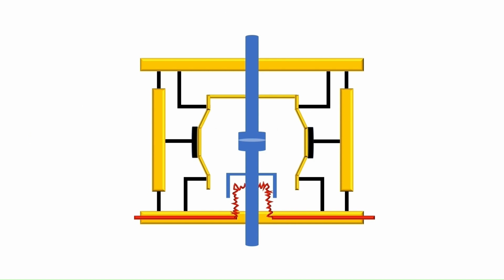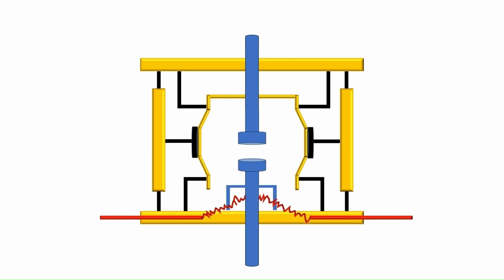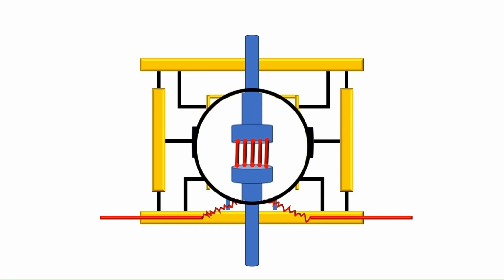When the fault occurs in the system, the contacts of the breaker are moved apart. When the moving and fixed contact detach, their entire surface does not separate simultaneously. During separation, the contact surface area gradually reduces before the contacts fully separate. As the contact area decreases, the current density increases at that point, creating a hot spot. At this hot spot, the contact metal vaporizes. So when the breaker contacts separate, an arc forms due to the ionization of the metal vapor released from the hot spot on the contact surface.